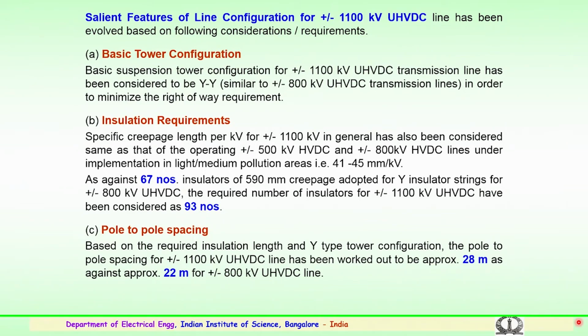The pole to pole spacing for 800 kV is typically 22 meters, which is being followed presently. If you go for 1100 kV the pole to pole spacing will be approximately 28 meters. So, several of these things are under study and estimated, so that the information is available in case you go for 1100 kV. A lot of manufacturers have to come forward in India. Again, manufacturing the equipment at this level is very, very important.